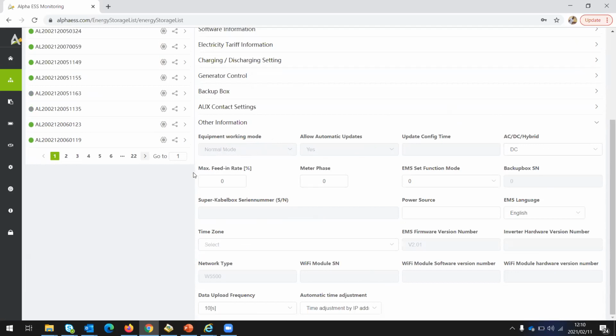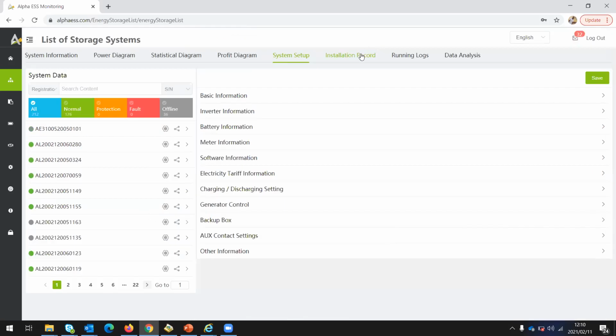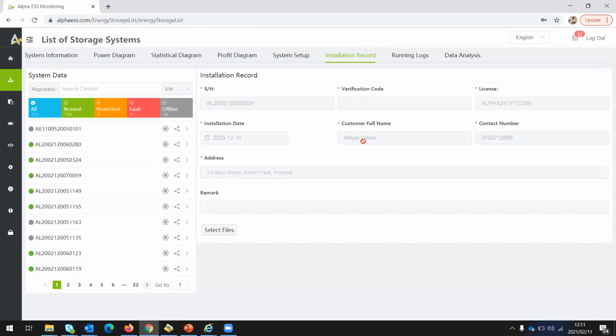And then one of the important settings under other information is the maximum feed-in rate. On this setting, that's where you set the amount of power you want to feed back to the grid. If you are not to feed back to the grid, you select 0. If you are to feed back, depending on how much power you want to feed back to the grid, you can calculate it as a percentage of 5 kilowatts, and then put that setting there. And then the installation record is basically the basic information, address and contact person of the system owner.